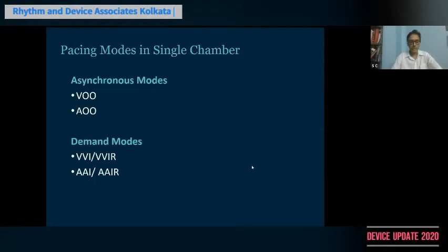If you have a single chamber device, that means a device in which a single lead is implanted into the right ventricle. There are two types of modes by which you can pace the device. One is called asynchronous mode, and the other is called demand mode. You can have asynchronous mode of pacing into the right atrium. You can have asynchronous mode of pacing in the right ventricle, and demand modes in the two chambers as well.